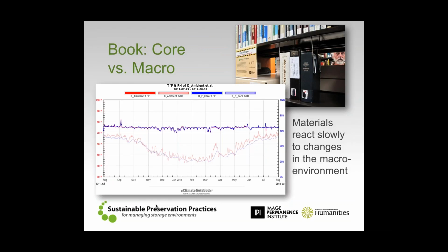is that materials react very slowly, especially in terms of relative humidity, to changes in the macro environment. Now, temperature changes, a book or archival material sitting in a particular storage area over the course of 8 hours might come to full equilibration with a one-time temperature change. But the thing to keep in mind is that when we run a system shutdown or even a setback, it's not a one-time temperature change. We're not changing the set point condition.